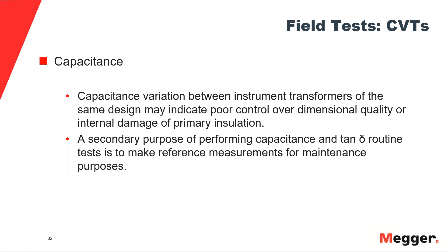Finally, we measure the capacitance of the elements in the voltage divider. Any variation between all those elements within one CVT will indicate either internal damage to the primary insulation or a defect from fabrication or poor quality control during manufacturing of the individual elements. Just as with tan delta, reference measurements for capacitance are recommended.